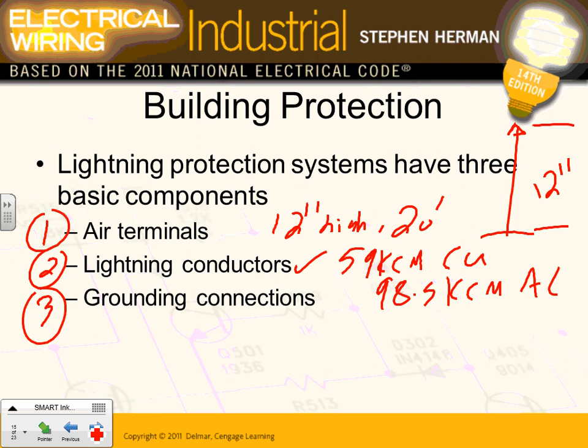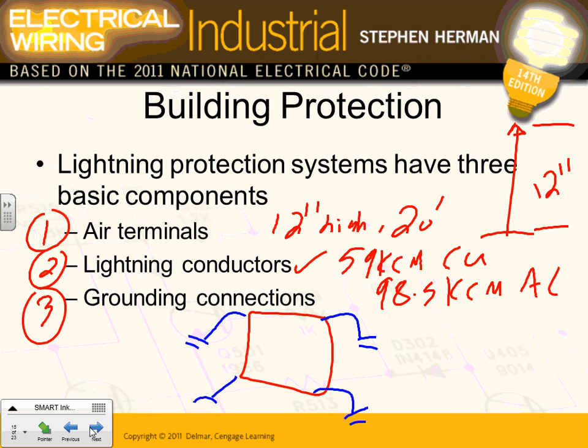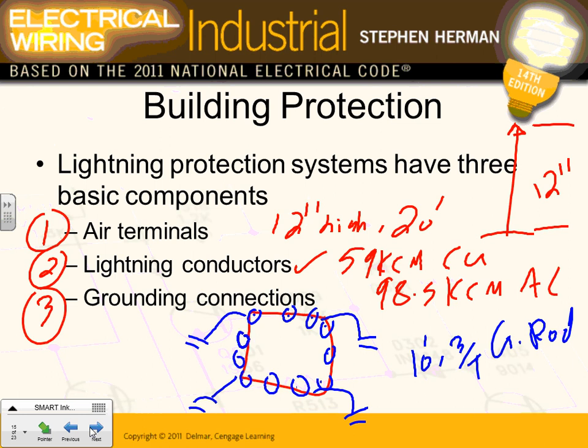For the grounding connection — for the whole building — we're going to provide a grounding connection at almost every corner. We'll take the spikes all the way down. We're going to have at least a 10-foot, 3/4-inch ground rod on every corner of the building. You connect all the spikes together and in the middle they usually put one every 50 feet. That's your design: air terminals, lightning conductors, ground connections.